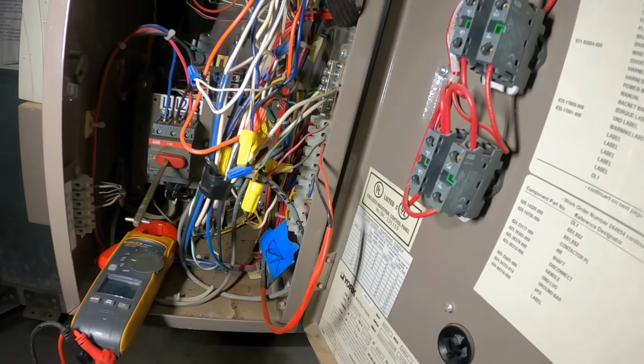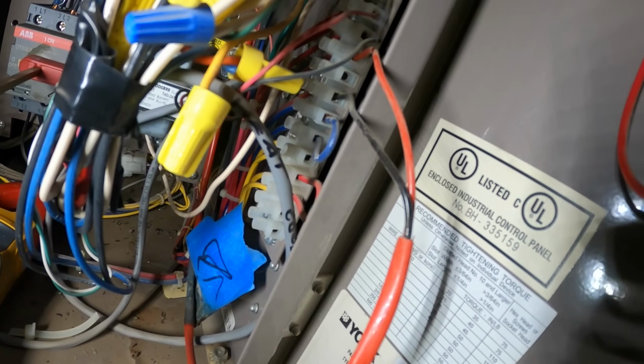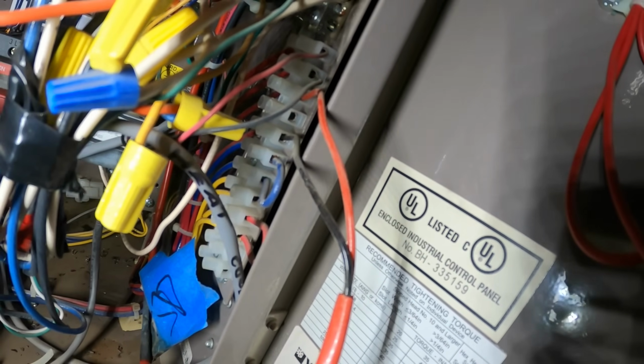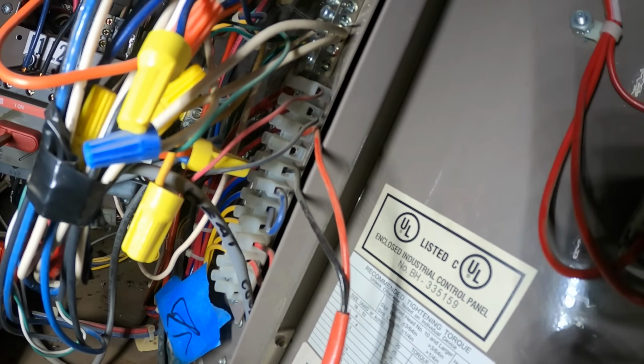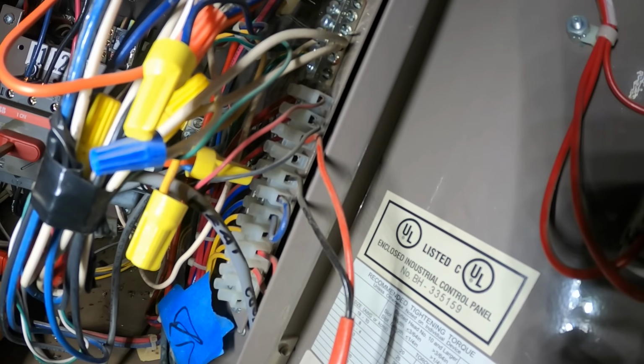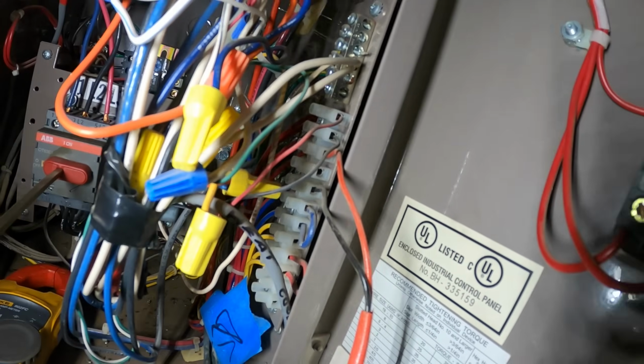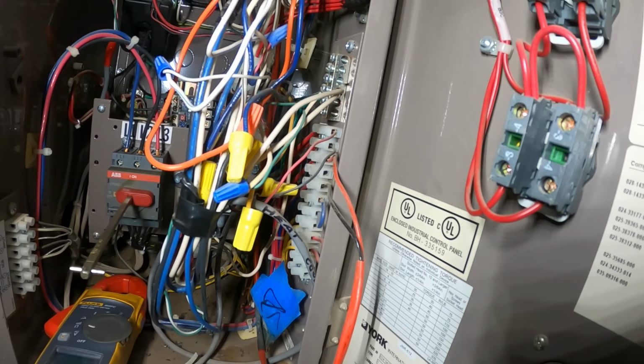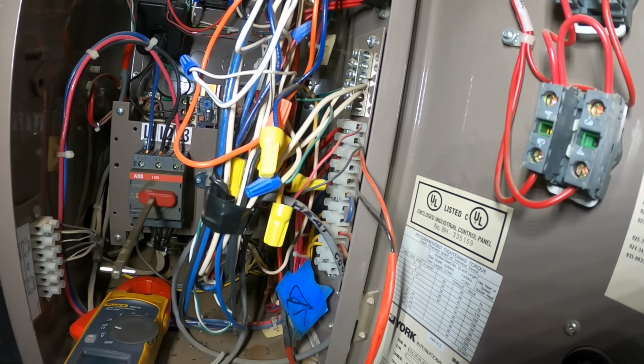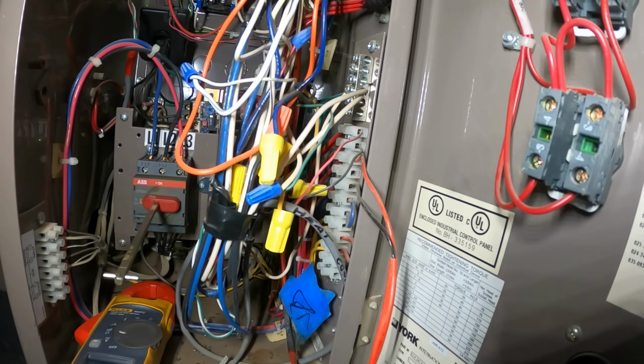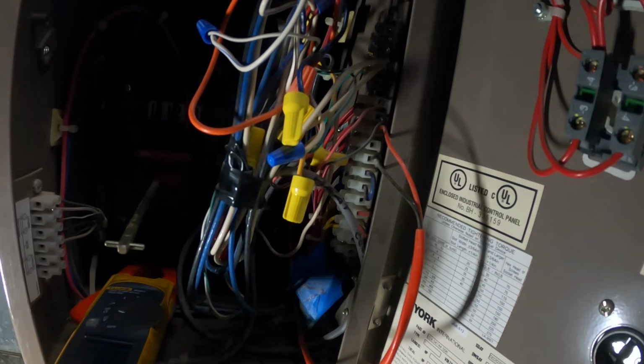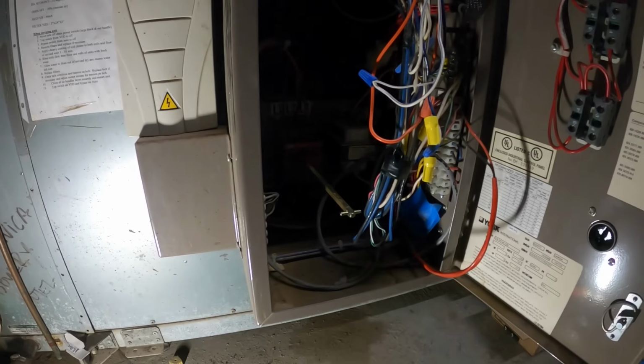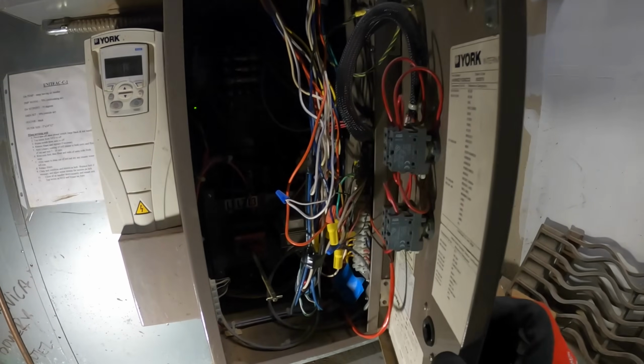Oh man, my thing wasn't recording, but I checked this fire cable. With the power off, I checked across the two, with it connected right there, and it was open. There was no continuity. Next thing you know, the engineer came in, and I was like, "Hey, man, did your fire alarms go off today?" And he was like, "Oh man, they were just testing it today." So I looked on the fire panel, and it was actually off.